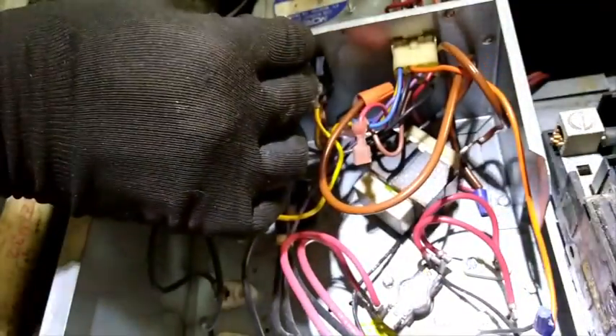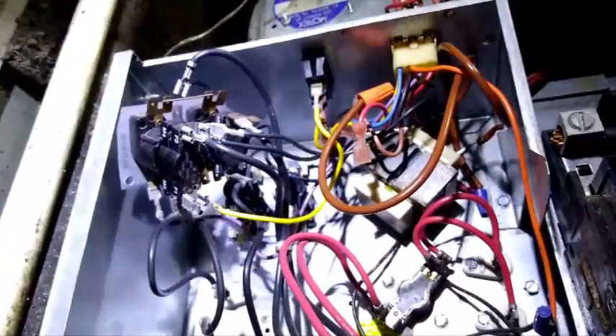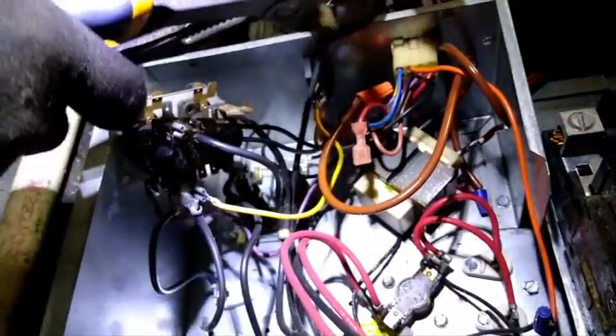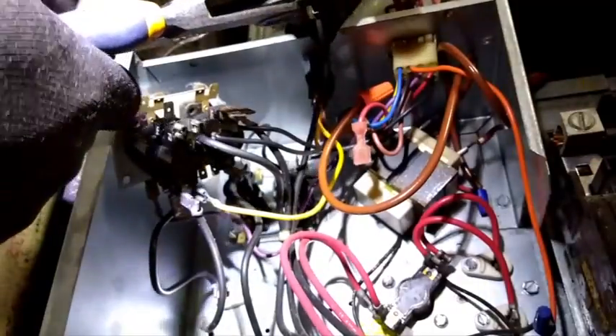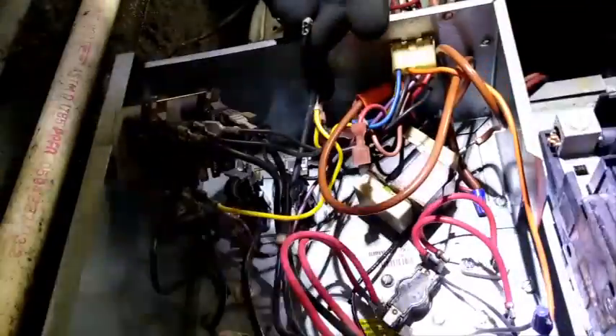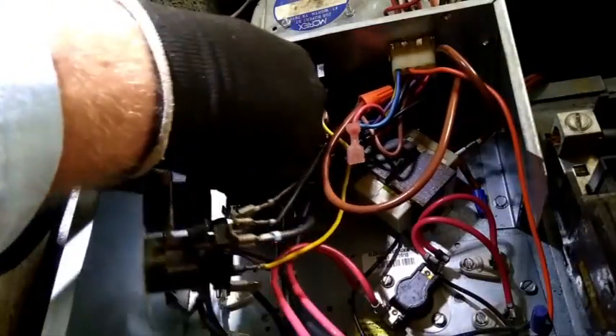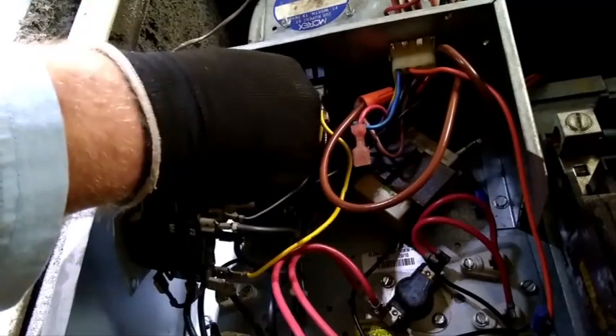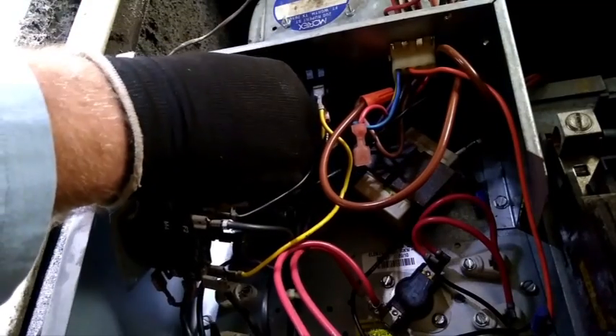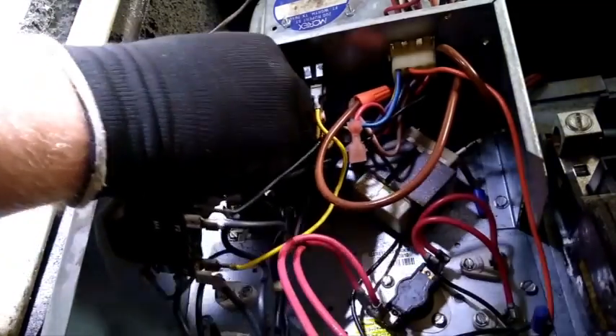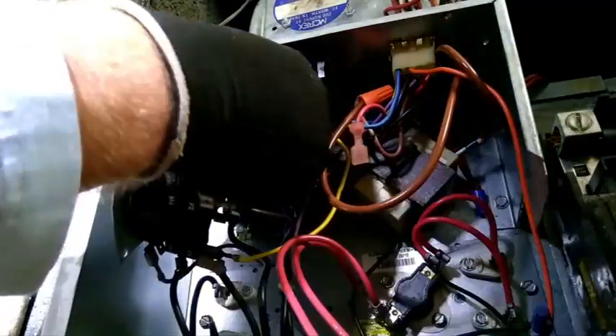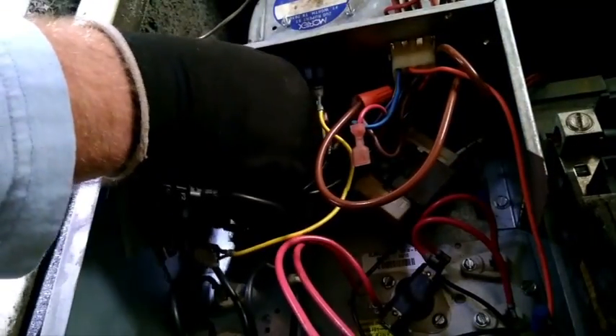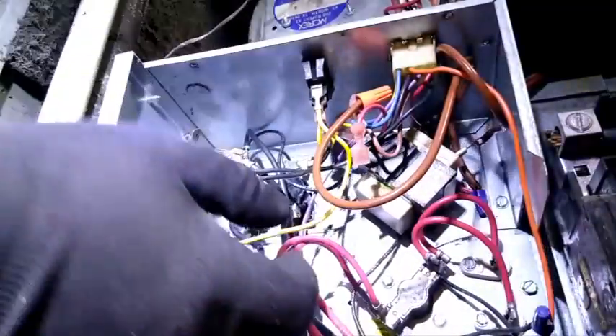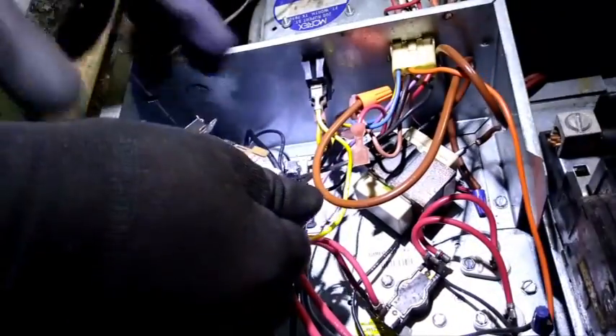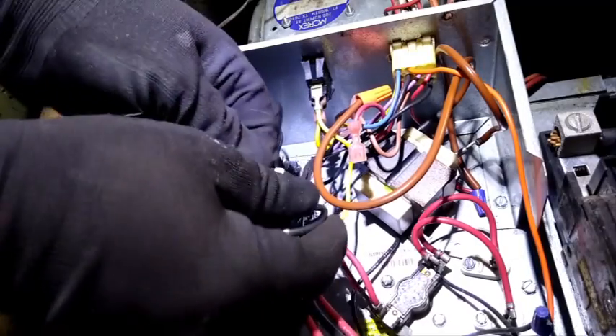And this is one of the nicer ones. There's some electric furnaces that have the breakers mounted in front of the controls, and they are a royal pain in the butt because it's almost impossible to test or work on anything without moving them out of the way. One reason I have the south wire is because it's easier to maneuver on those units, because trying to get a multimeter lead in there is near impossible—you're just about guaranteed to shock the crap out of yourself because you have those 240 breakers right in the front.